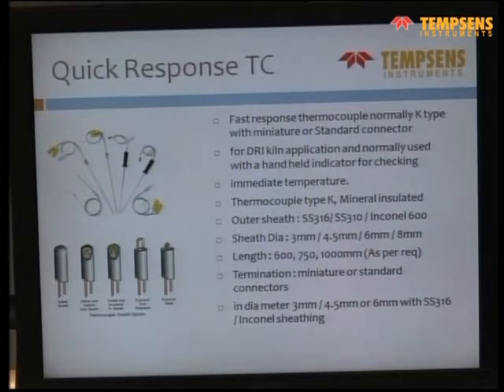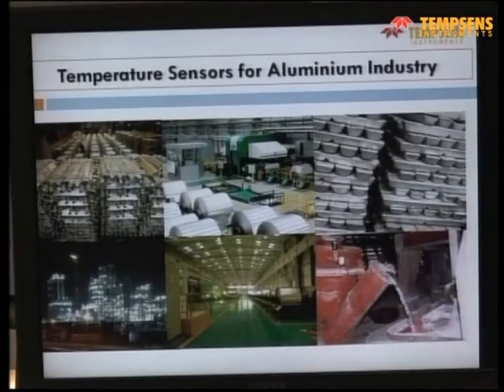In the case of the sponge plant, they have a rotating kiln, and they use quick response thermocouples which are grounded junction. So a person is putting it inside after a few cycles. He is putting it inside manually and checking the temperature. For each rotation he is just putting it inside and taking it out. So it's more like a manual process. All the sponge iron plants are using what is called a QRT, quick response thermocouple. They are using grounded ones.